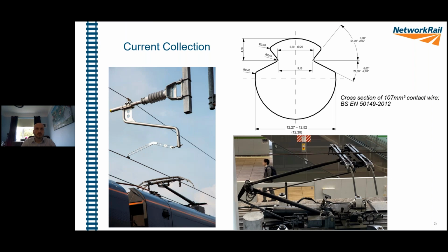It's important, as Martin mentioned before, that we maintain a good contact with this. So there is a 90 newtons upwards force which is maintained by a pneumatically operated pantograph system, which in itself also allows for damping for when the contact wire moves up and down vertically.